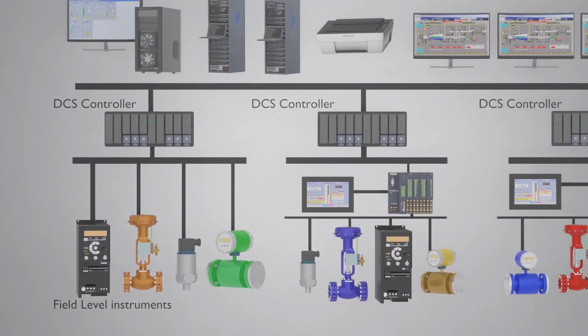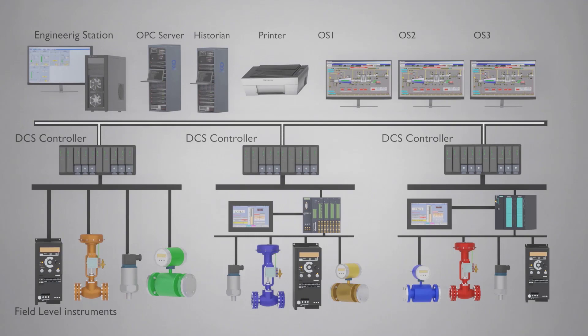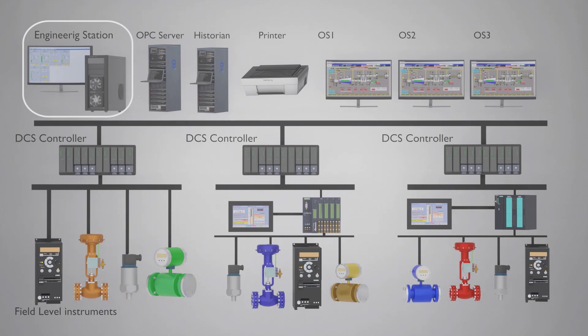These controllers are connected to one network that has different systems on it. One of them is the engineering workstation. If you want to create graphics on operator screens, or write code on individual controllers in different areas, you can use the engineering workstation to modify programs on any specific DCS controller — without going to the site to plug in a laptop. You can sit in the control room and use the engineering workstation to modify code on all DCS systems.